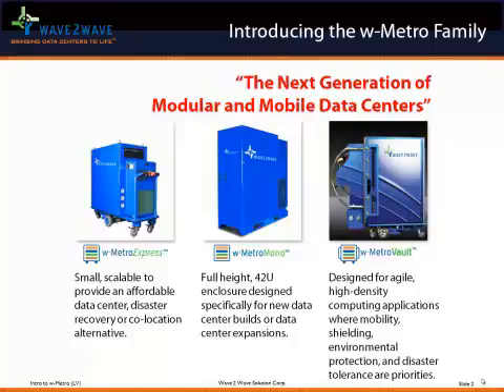The W Metro Mono is a 42U enclosure. It is NEMA 4 rated. It has a 42,000 BTU air conditioning system. It is mobile, but not self-propelled. The mobility comes in the form of using a pallet jack to move this unit around. It is slightly under 7 feet tall. It provides you with 12 kilowatts of IT load, and again allows you the ability to expand and to consolidate your current racks in your data center should you need to do so. We'll talk a little bit more about that as we go along. Remember, we talked about 12 kilowatts of IT load in this particular unit.